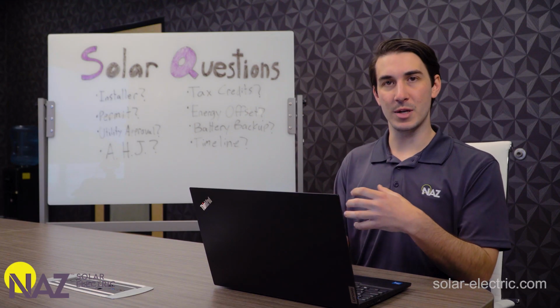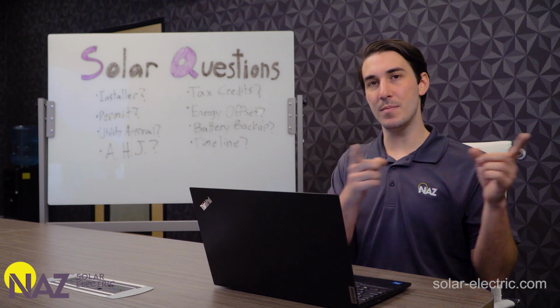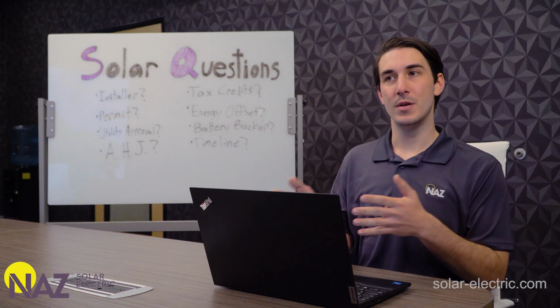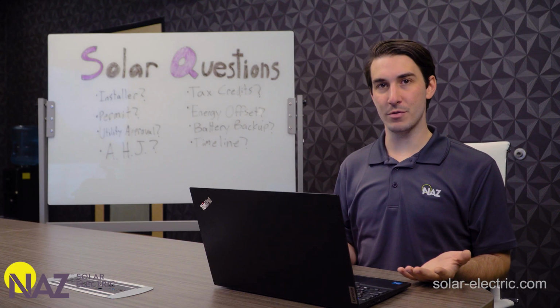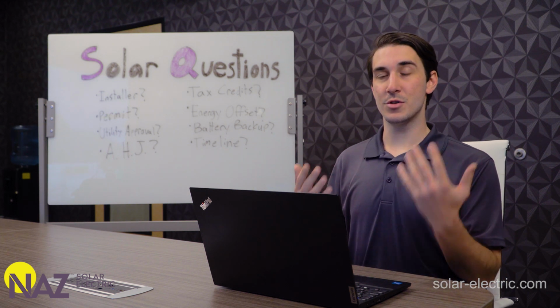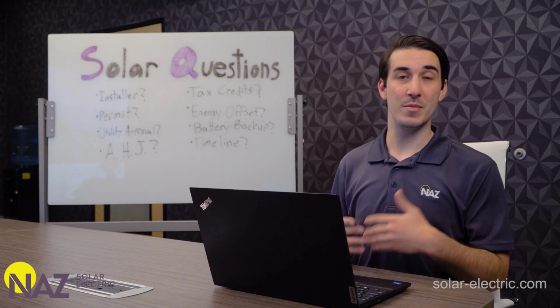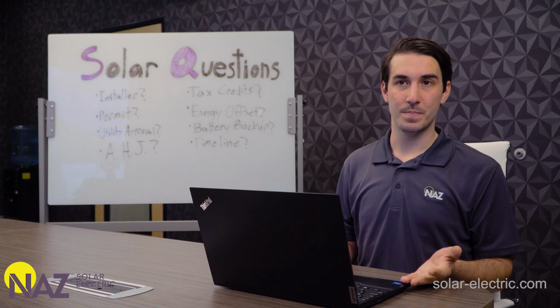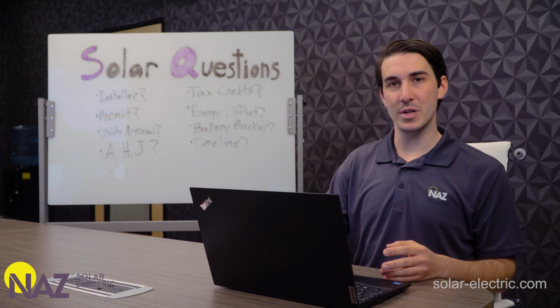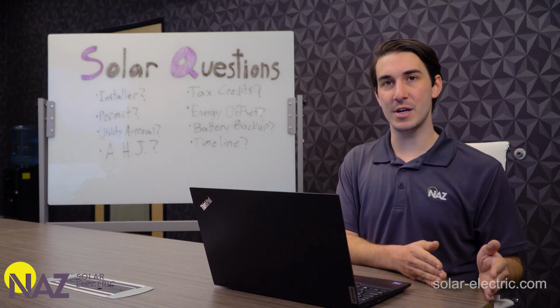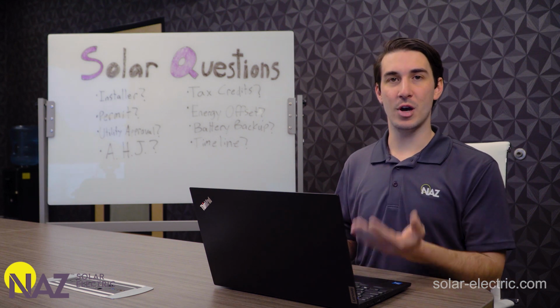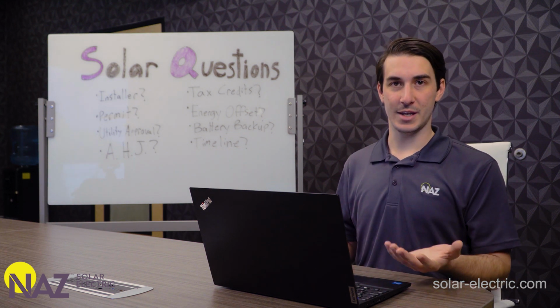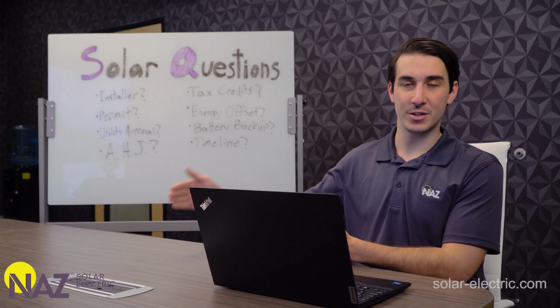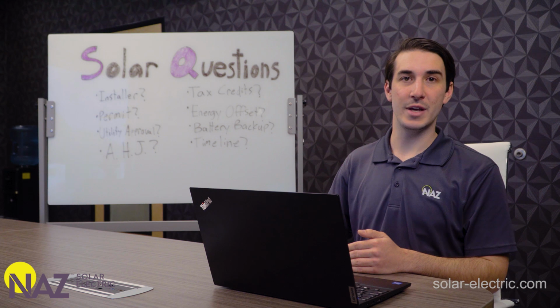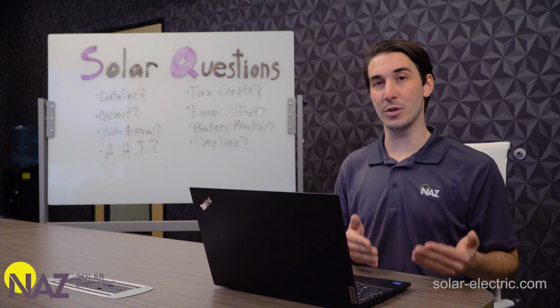Depending on how long the permitting process takes, by the time that's done and approved, maybe you're ready to order the equipment, but certain components might not be available, or there's an extended lead time for something. So now you have your plans and permits already drawn up from the original design, but you're making a change to accommodate something that's not available. And guess what? Now that means you have to go back to the AHJ, back to your utility company, and resubmit those plans with the current available equipment.